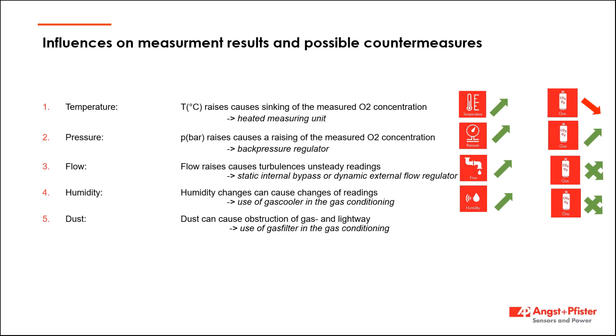So after talking about all these influences, we really also need to address the outstanding advantages of PAROX, because if you take the right countermeasures for those influences, you might have really outstanding advantages. First of all, the principle is fully linear. This means you need only a zero and a span calibration to calibrate the sensor. Then you have a very low cross sensitivity with other gases. You have no maintenance, as there are no wearing parts.